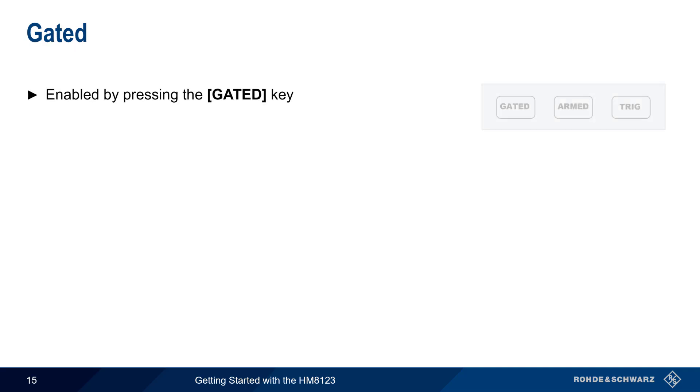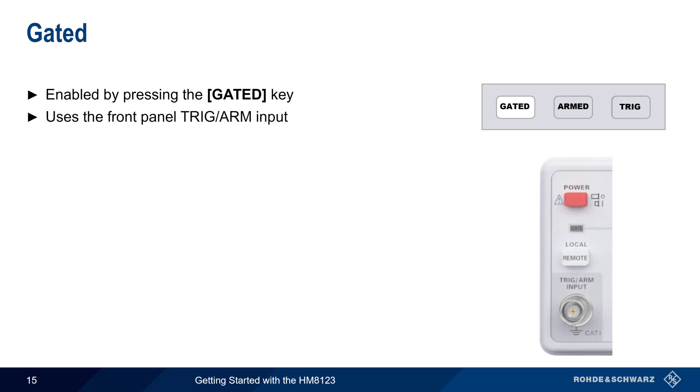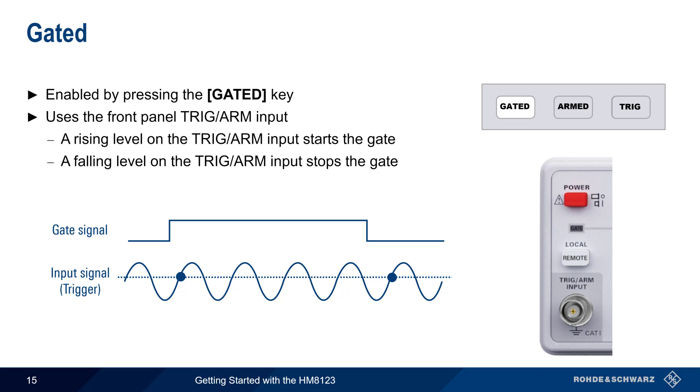The Gated function is enabled by pressing the Gated hard key. Gated measurements use the Trig Arm BNC connector on the front panel. In Gated mode, a rising level at this input starts the measurement gate the next time the trigger condition is met. And a falling edge on this input stops the gate. The gate time is therefore determined by these external signals. And this external signal has a higher priority than any other configured gate settings.